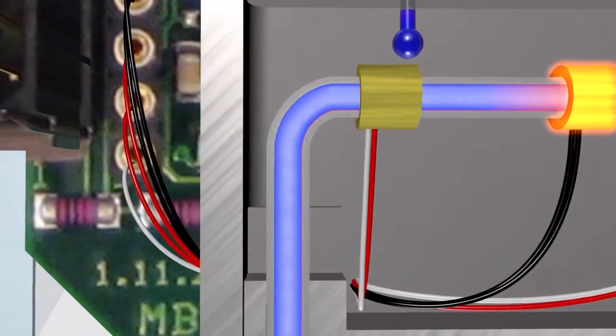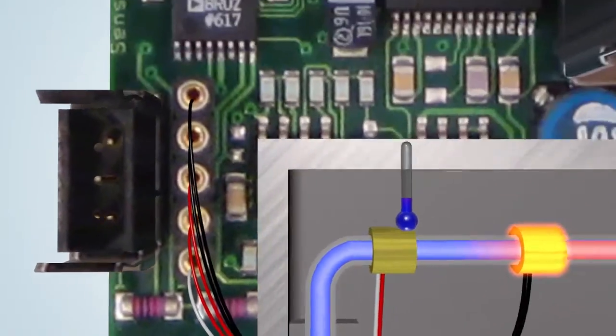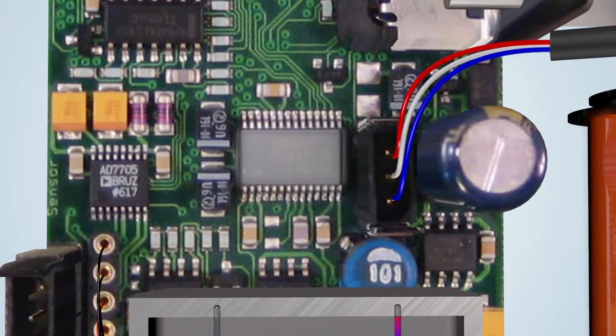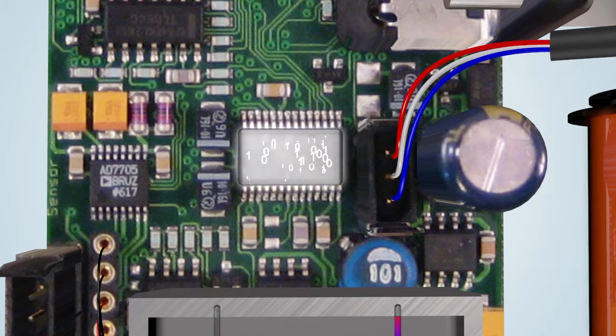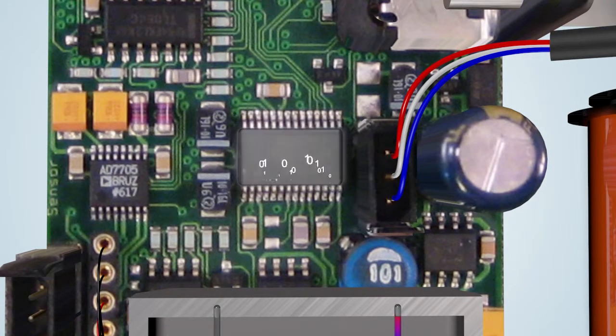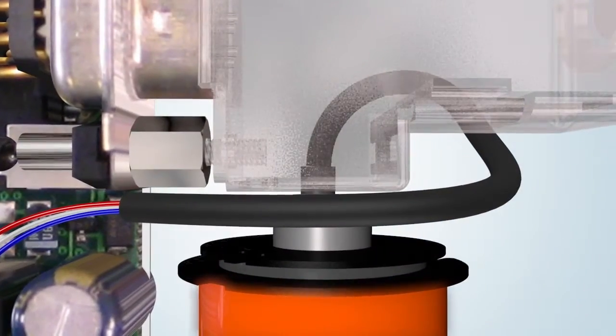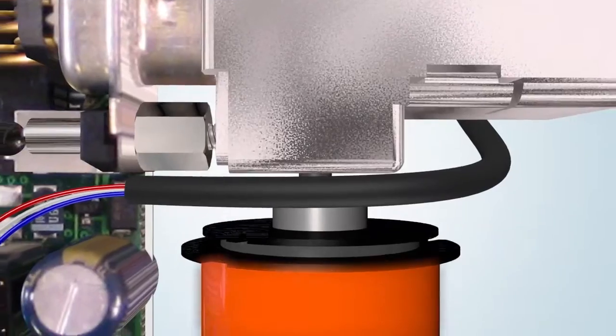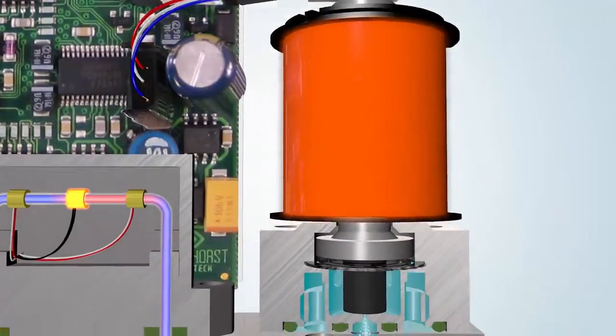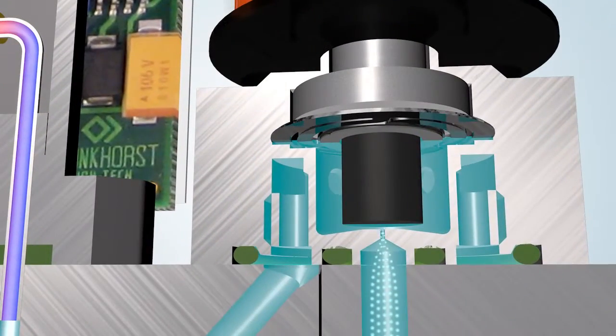The signal from the sensor is compared with the desired value in the microprocessor. The electric current of the coil is adjusted so that the distance between the plunger and the orifice is exactly right for controlling the desired quantity of gas.